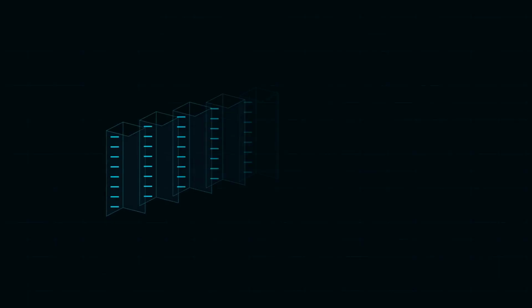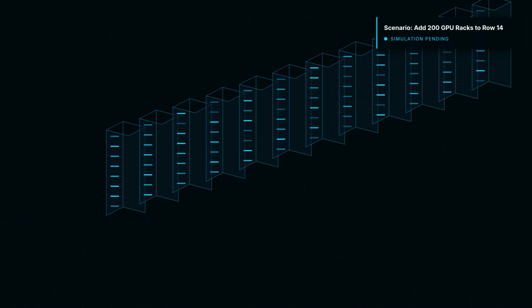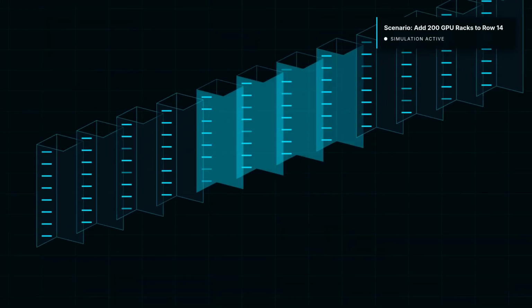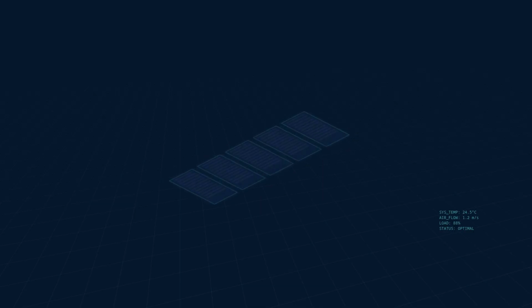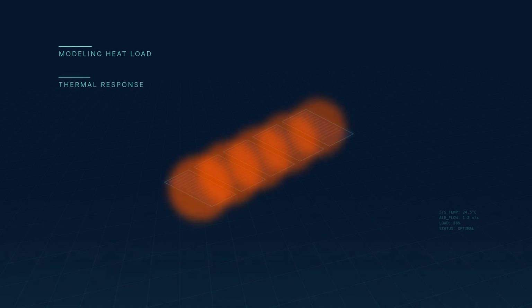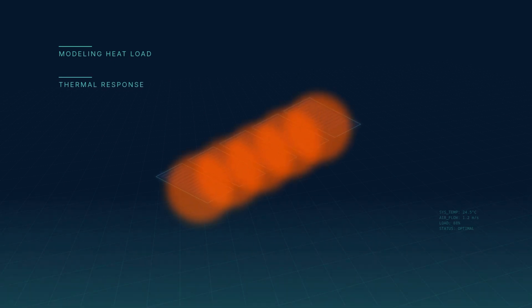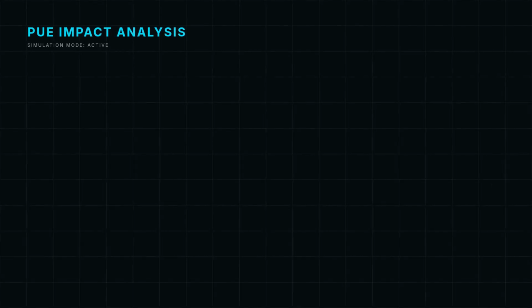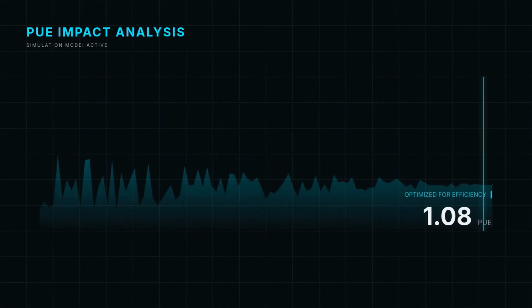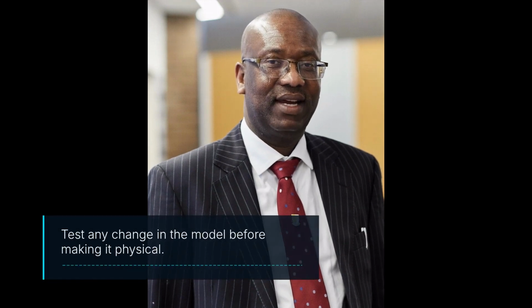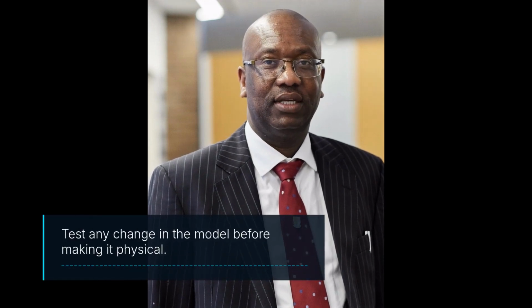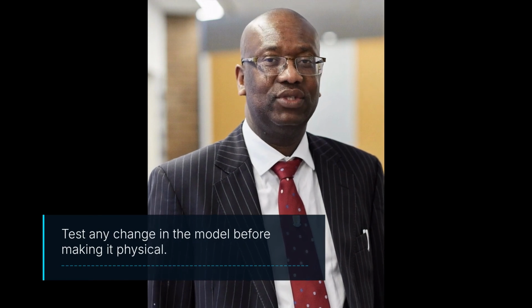When the capacity team needs to add 200 more GPU racks to a row, they run the simulation in the twin first. The twin models the additional heat load, the CRAH response, and the impact on the cold aisle temperature profile. We can see the impact on PUE before a single piece of hardware is ever installed on the floor. This capability allows us to test and validate any change virtually, ensuring total operational safety.